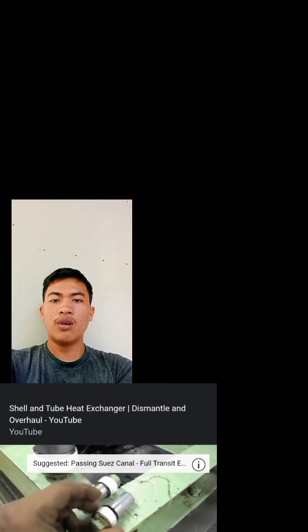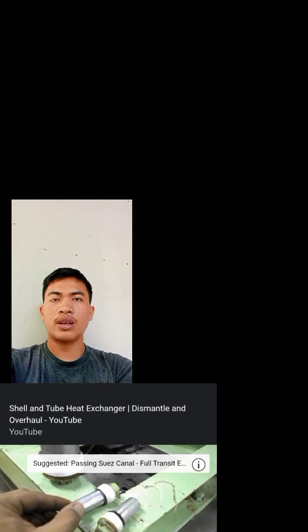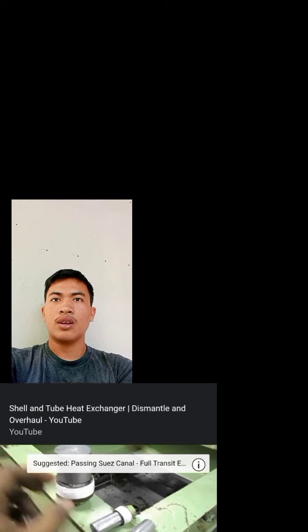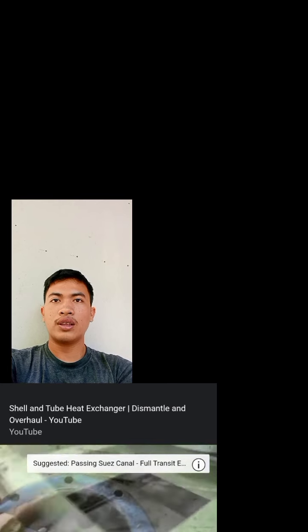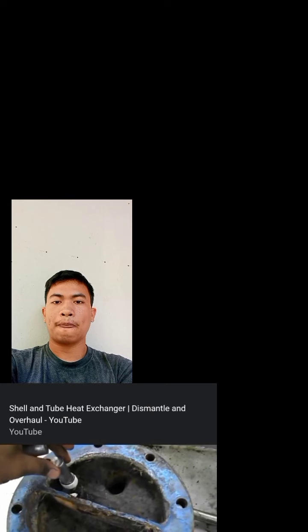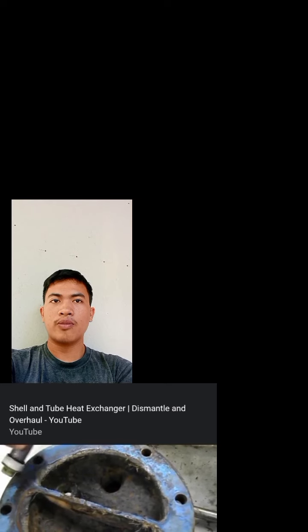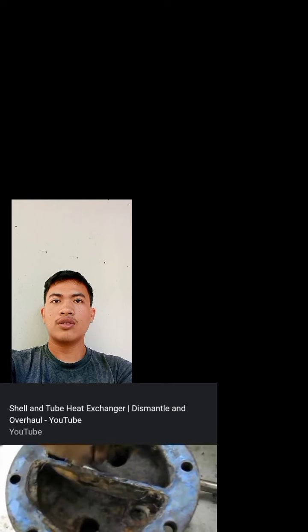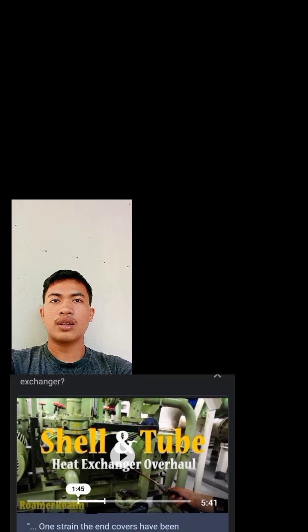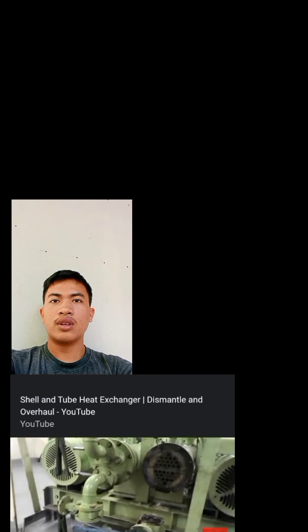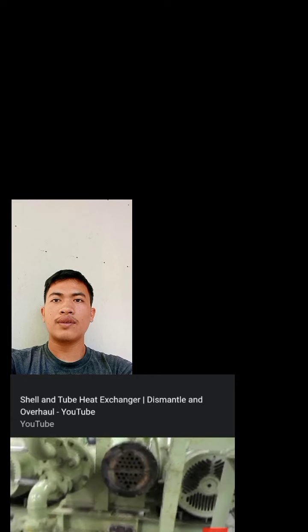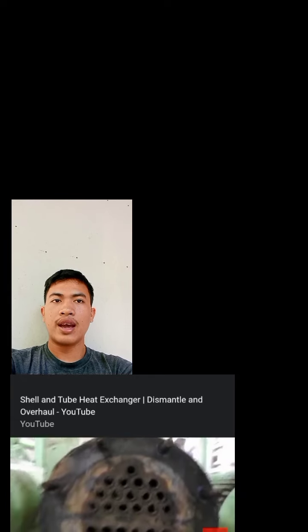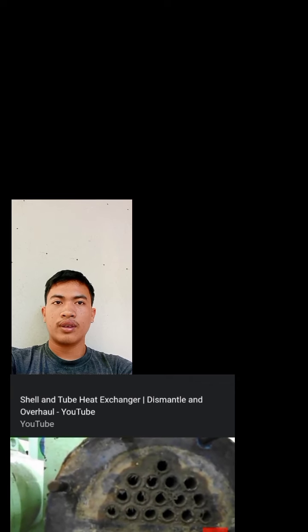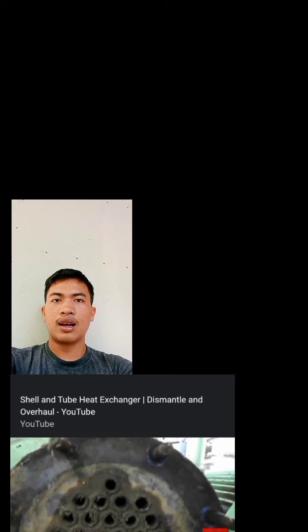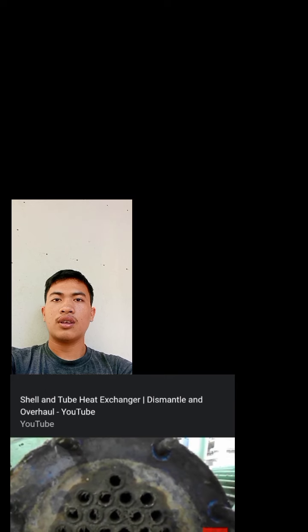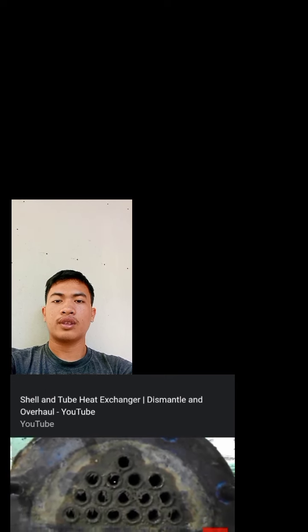The working fluid in the vacuum pump cooler is seawater, and no matter what kind of filters and anti-fouling system you have on your ship, some contamination will definitely find its way to the coolers. This actually does not look so bad, because as you can see, most of the tubes are still clear. Now, as already mentioned, the working fluid is seawater, so to protect the material from corrosion, we have some sacrificial anodes fitted to the body, besides the general cleaning that is carried out. It is absolutely important to check the condition of these anodes, and by experience you would know when you are replacing them in the tube type heat exchanger.